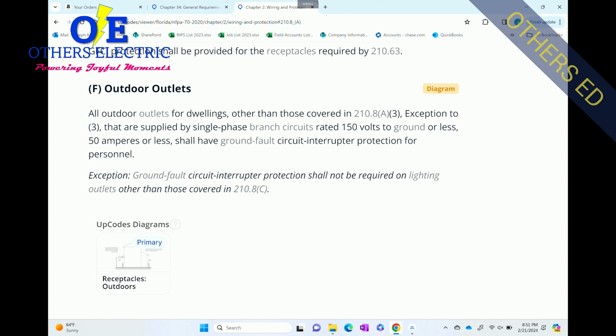So let's break that down. First thing they're talking about is all outdoor outlets for dwellings. So dwellings is your 1 and 2 family, right? Your single family home, or your two family home, your duplexes and things like that. And what it's saying here is that are supplied by single phase branch circuits. So that's either a single pole breaker or a 2-pole breaker. Don't get confused by the single phase. Single phase also includes your 2-pole breakers.